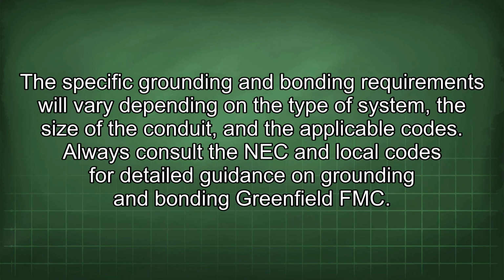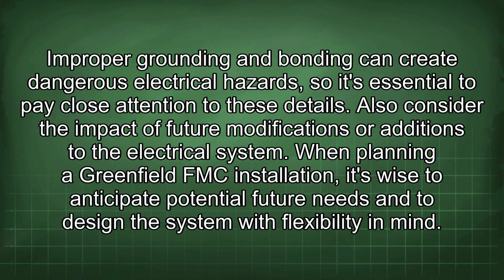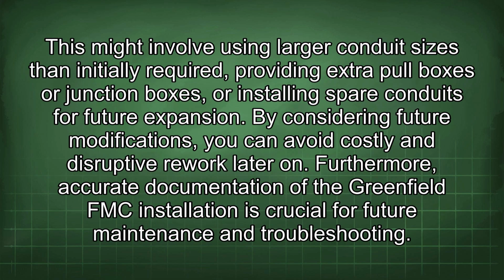The specific grounding and bonding requirements will vary depending on the type of system, the size of the conduit, and the applicable codes. Always consult the NEC and local codes for detailed guidance on grounding and bonding Greenfield FMC. Improper grounding and bonding can create dangerous electrical hazards, so it's essential to pay close attention to these details. Also consider the impact of future modifications or additions to the electrical system. When planning a Greenfield FMC installation, it's wise to anticipate potential future needs and to design the system with flexibility in mind. This might involve using larger conduit sizes than initially required, providing extra pull boxes or junction boxes, or installing spare conduits for future expansion. By considering future modifications, you can avoid costly and disruptive rework later on.